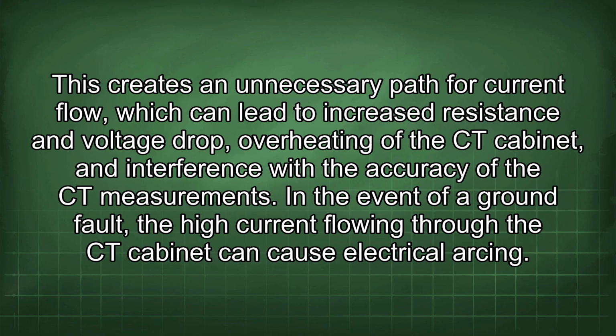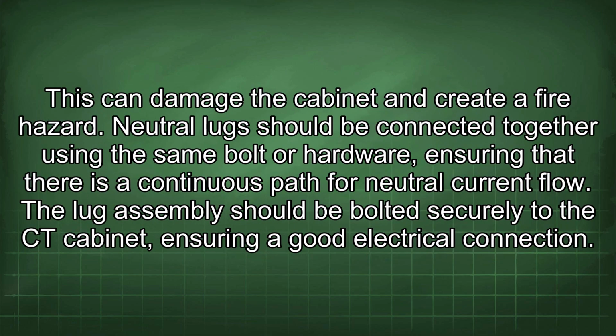This creates an unnecessary path for current flow, which can lead to increased resistance and voltage drop, overheating of the CT cabinet, and interference with the accuracy of the CT measurements. In the event of a ground fault, the high current flowing through the CT cabinet can cause electrical arcing. This can damage the cabinet and create a fire hazard.